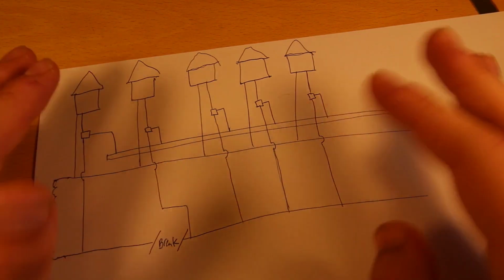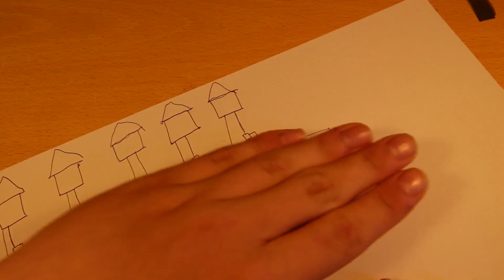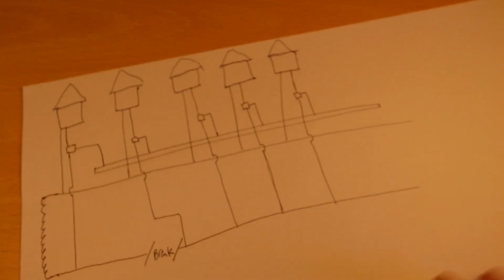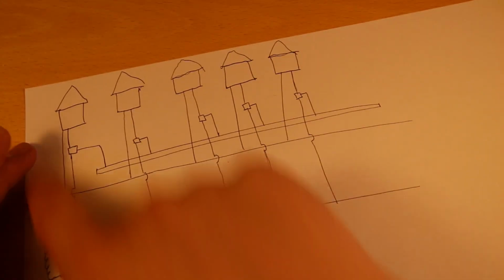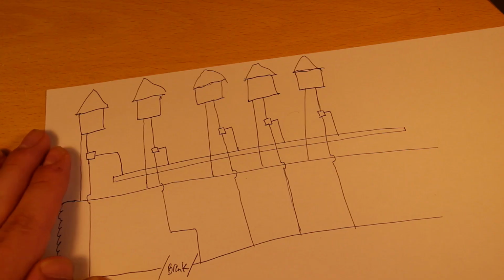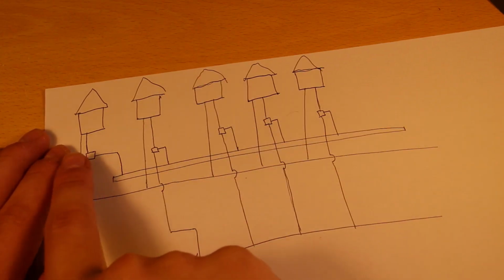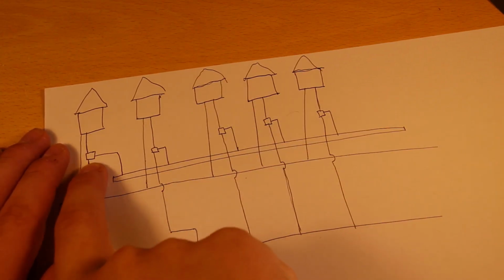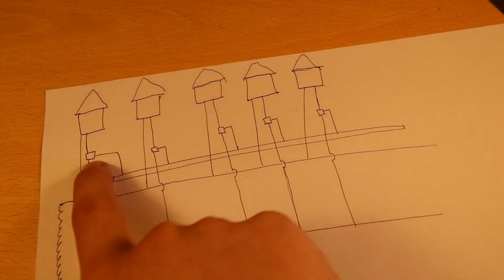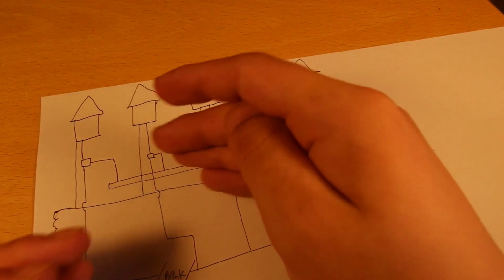The other potential failure mode is if there is no gas or water or some conductive path for the neutral current to divert via. What will happen is, it will not be able to return to the transformer, so you will end up with this terminal here being live with reference to the actual earth. Therefore your earth is live with reference to the actual earth.